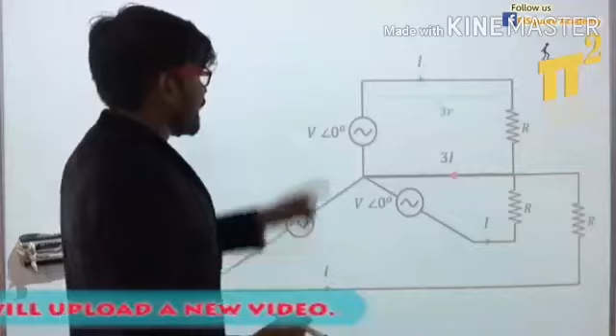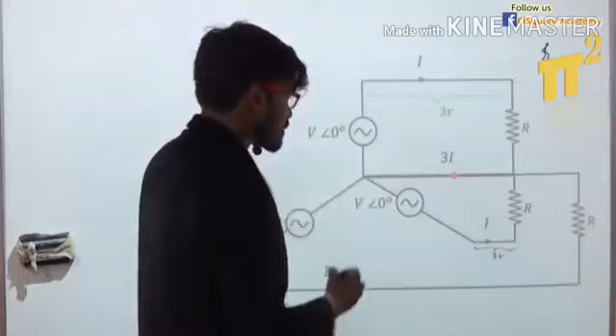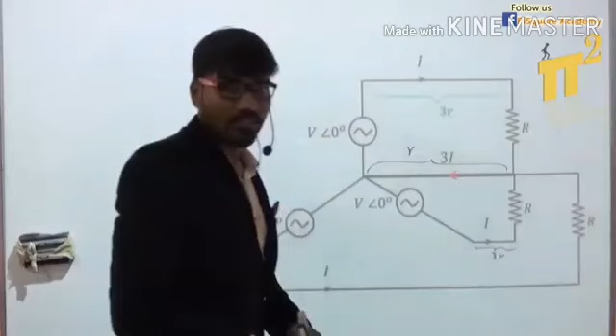Current is I here, so resistance is 3R, same for each of the 3 phase wires of 100 kilometers length. But this common return conductor, also 100 kilometers, carries a current of 3I, since all 3 currents return through it. So it has a larger cross-sectional area, hence less resistance, just R.